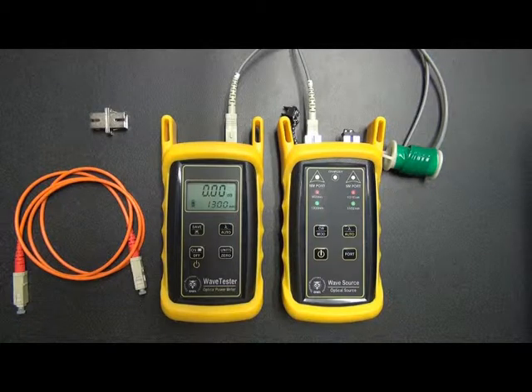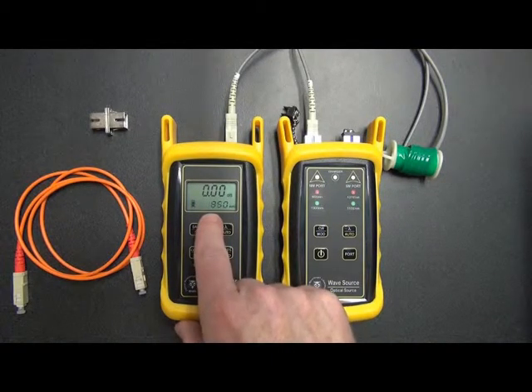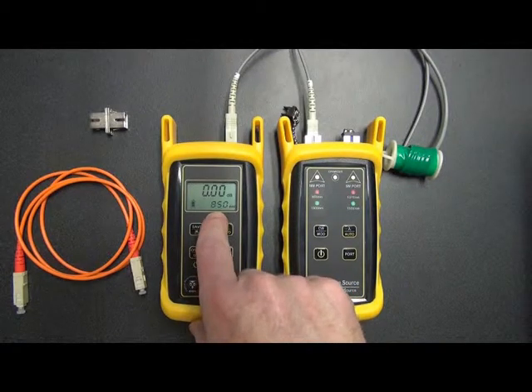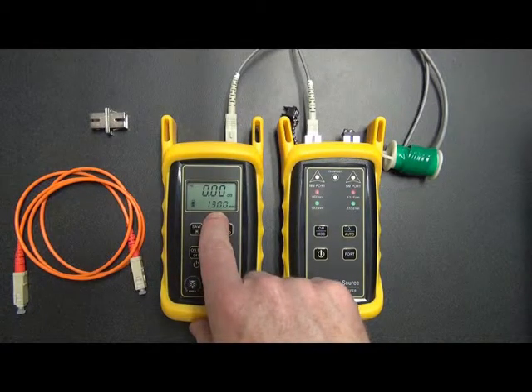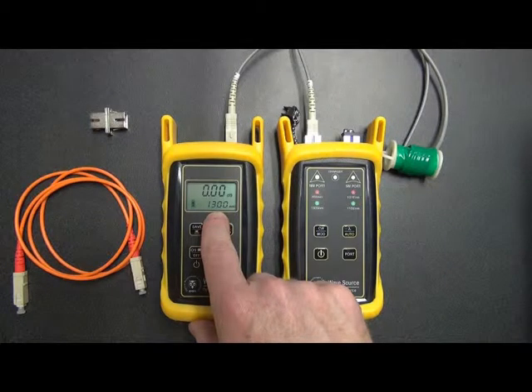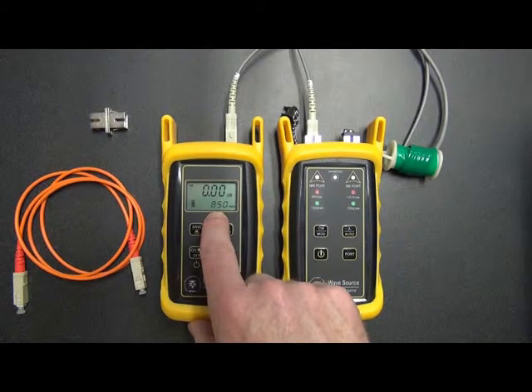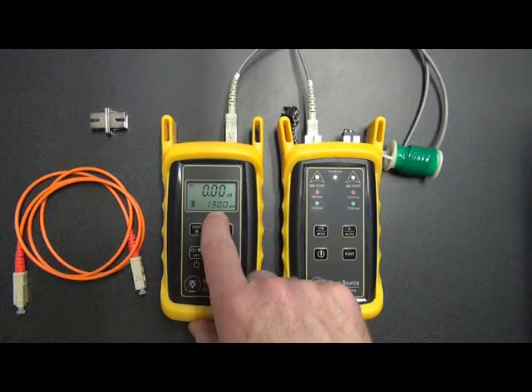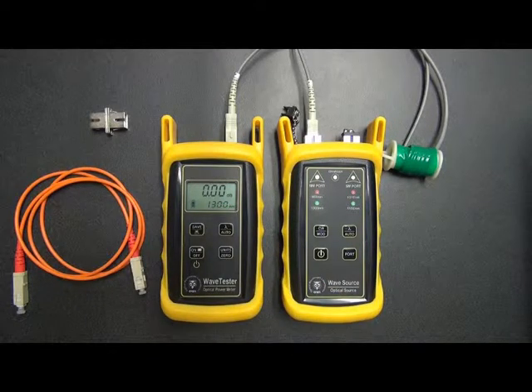And we watch the WaveSource for a few seconds just to make sure that it's switching back and forth between green and red. Okay, going back to the power meter, we will see that it's not saying auto anymore, but it's switching between the two wavelengths. So there's 850, 1300. 850, 1300. And notice both of the readings are saying 0 dB. What this means is that we have successfully zeroed out our equipment, and the patch cable is good, and the equipment is working properly together.